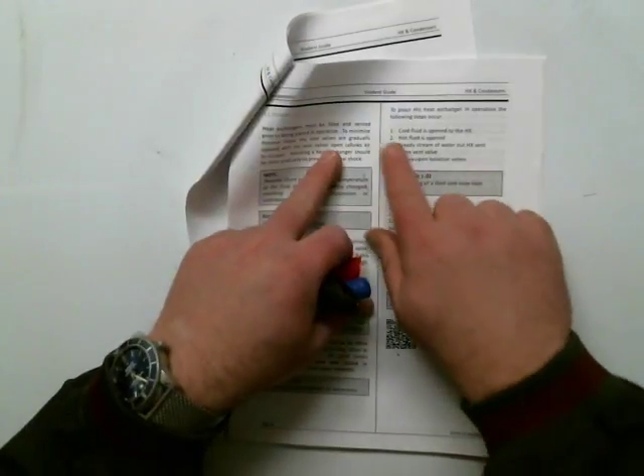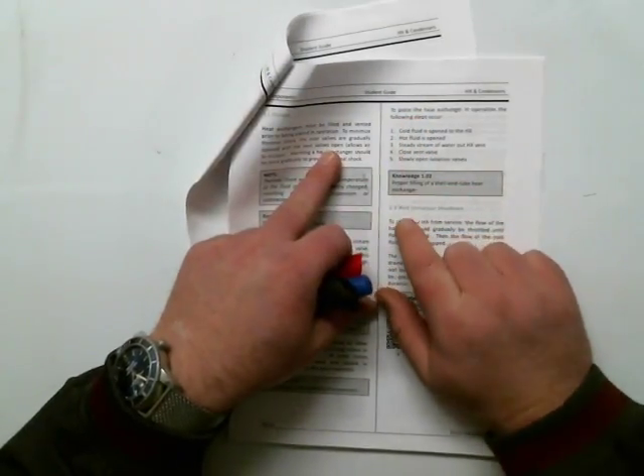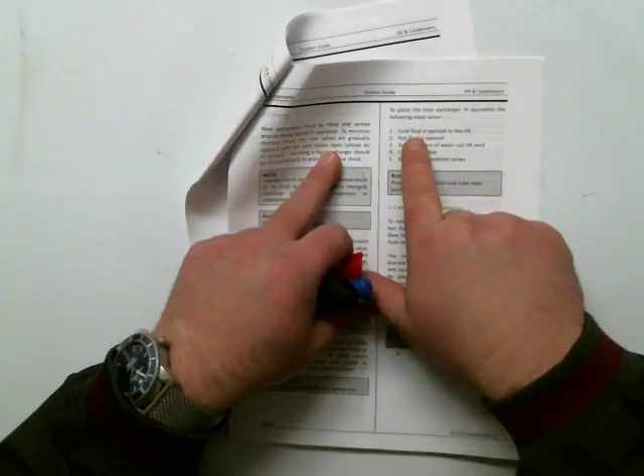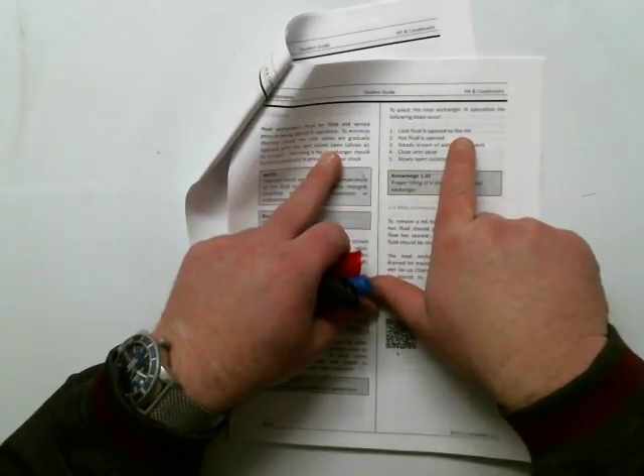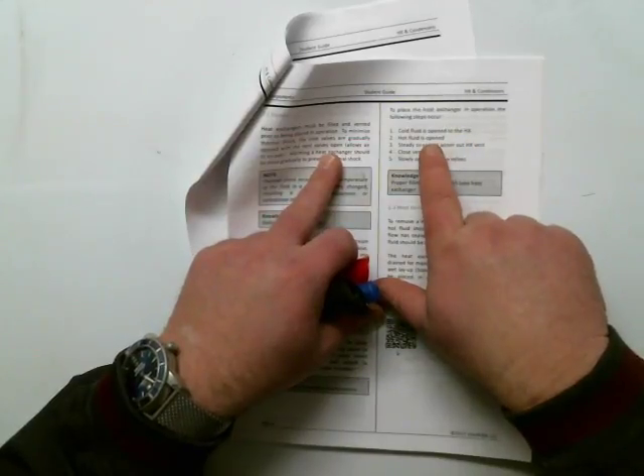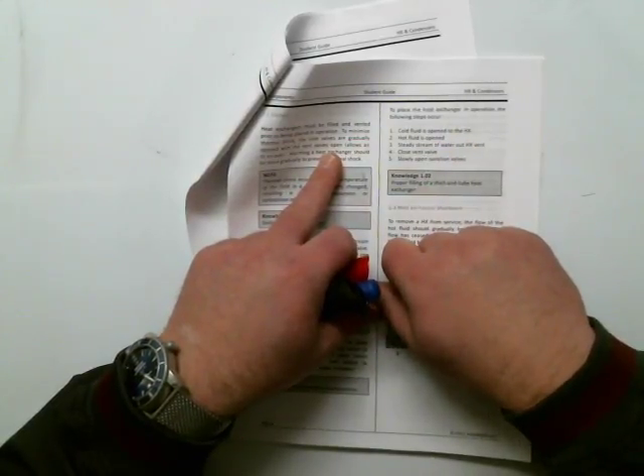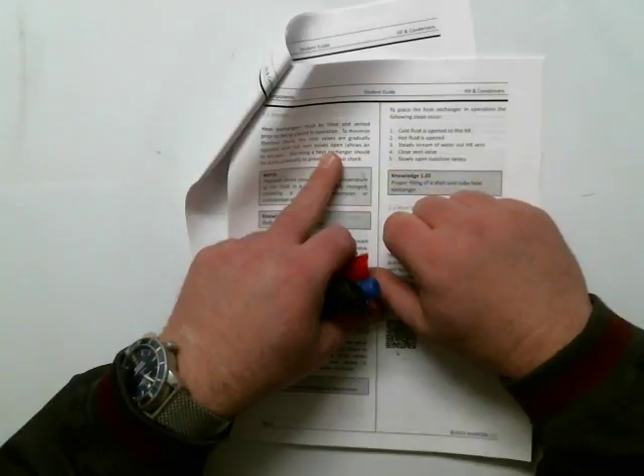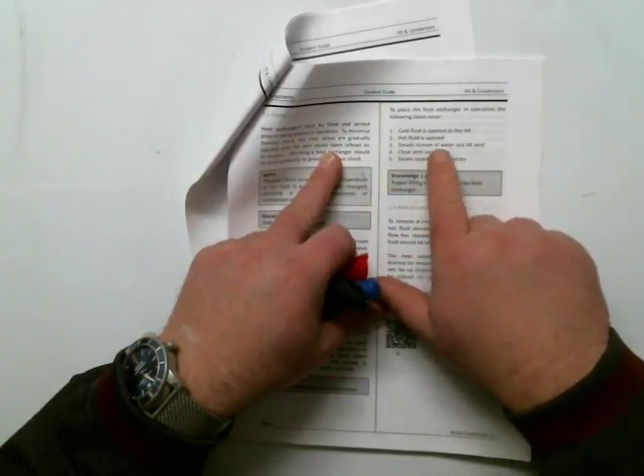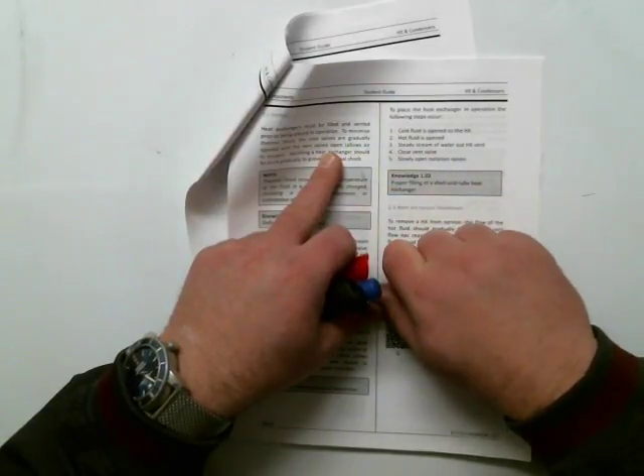So up here on the upper right, proper filling and venting of a heat exchanger, it gives us the sequence at which we will start up. And it says cold fluid is opened to the heat exchanger gradually and filled and vented, and then the hot fluid is introduced, and it's introduced gradually to prevent thermal shock till we get a steady stream of water, and then we'll close the valves.